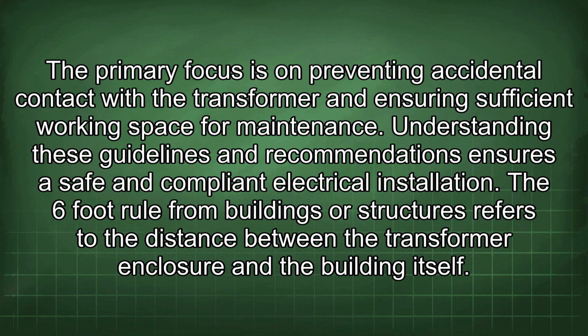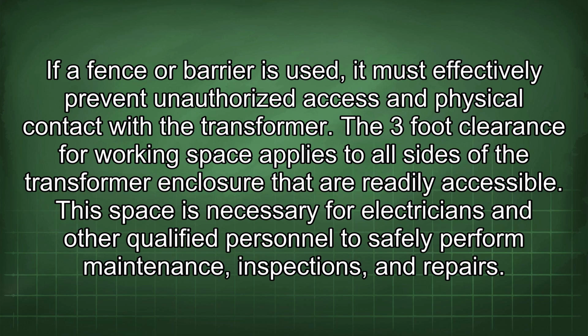The 6-foot rule from buildings or structures refers to the distance between the transformer enclosure and the building itself. If a fence or barrier is used, it must effectively prevent unauthorized access and physical contact with the transformer. The 3-foot clearance for working space applies to all sides of the transformer enclosure that are readily accessible. This space is necessary for electricians and other qualified personnel to safely perform maintenance, inspections, and repairs.